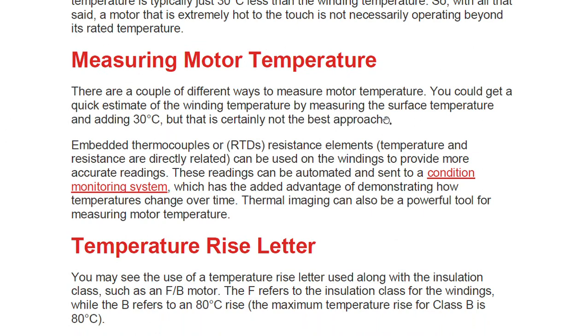There are a couple of ways to measure motor temperature. You could get a quick estimate of winding temperature by measuring the surface temperature and adding 30°C, but that is certainly not the best approach. Embedded thermocouples — RTDs, where resistance and temperature are directly related — can be used in the winding to provide a more accurate reading. These readings can be automated and sent to a condition monitoring system.